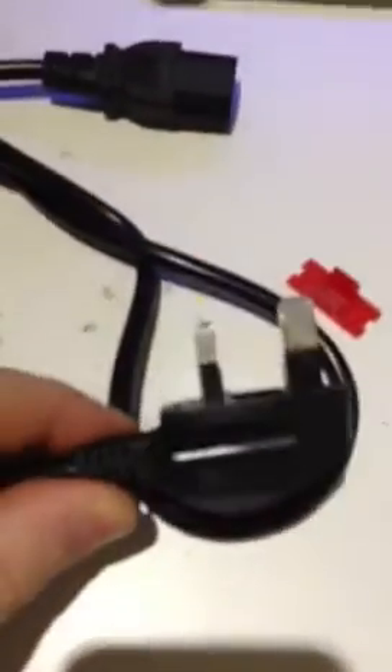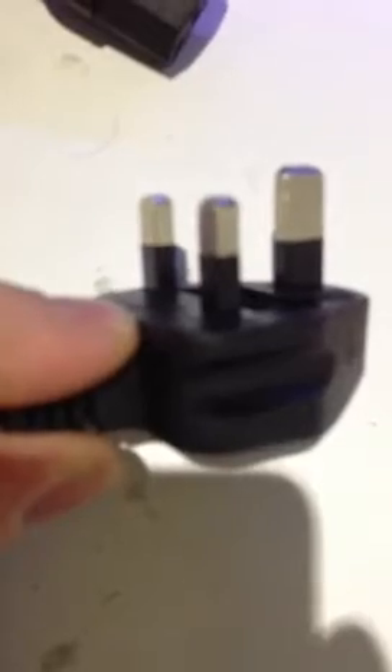Now we look at the plug itself. Standard on British Standard plugs is the insulation sleeving around the live and the neutral pins. But unfortunately on this counterfeit one we actually have insulation sleeving around the earth pin. To a British Standard plug, when carrying earth, the earth pin should be fully metal. As you can see on the genuine lead, this one has a metal pin for the earth.